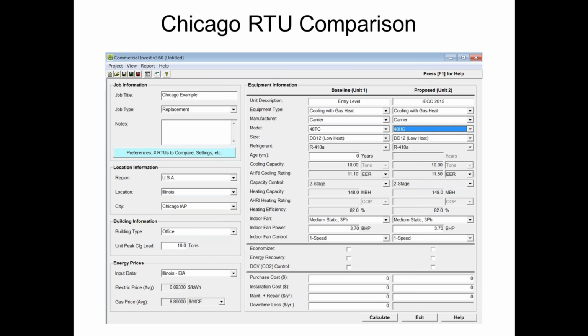It is a Carrier software tool, but it's generic. It has multiple manufacturers in there. It just uses the published ratings of those manufacturers. What you can do is run different examples of either 2 brand new units and see which one is better in terms of efficiency, or an old unit versus a new unit, which is very commonly what this is used for. I tell it what my cooling load is on the bottom left-hand side over here. In my case, I told it I want to use the EIA energy data. I could have punched my own utility data in, but taking the state average from the Energy Information Administration is just easier, so I did it that way.